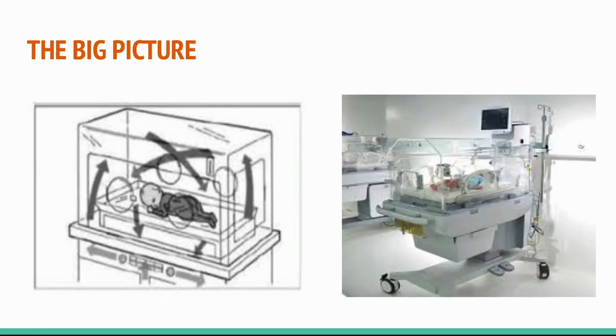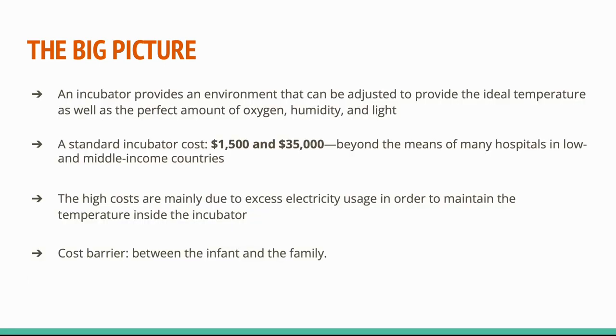This is what a functional incubator looks like. The shape and size of the incubator, along with its product design, focuses on maximizing heat efficiency and minimizing heating cost. An incubator provides an environment that can be adjusted to provide the ideal temperature as well as the perfect amount of oxygen, humidity and light. A standard incubator found in a newborn intensive care unit costs between $1,500 and $35,000, beyond the means of many hospitals in low and mid-income countries. The high costs are due to excessive electricity usage in order to maintain the temperature inside the incubator. The cost being a barrier between the infant and the family, we plan to optimize it using heat transfer methods learned in our second year engineering courses.